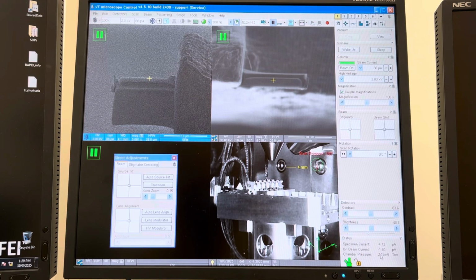The equivalency in millibar is a little bit higher, but ultimately we can get this into the high E-7 torr range. And if the chamber was already under vacuum when I came in and loaded the samples and then pumped it back down, I should have been able to get this easily into the mid E-6 torr range within just a few minutes.